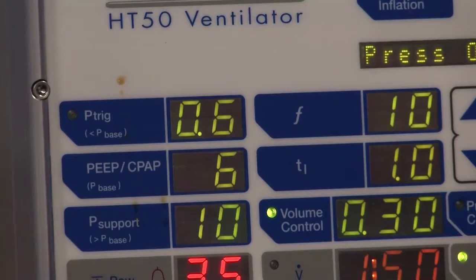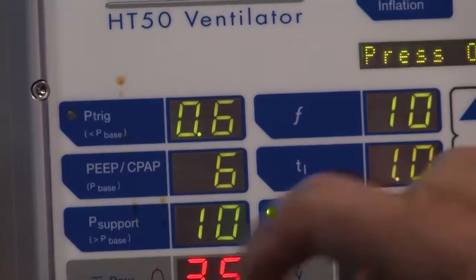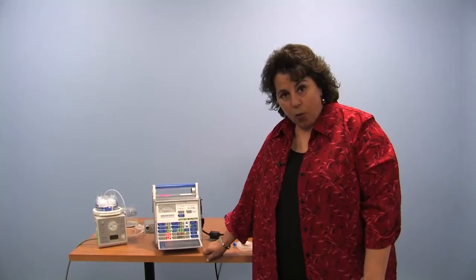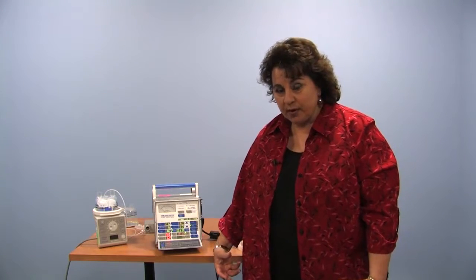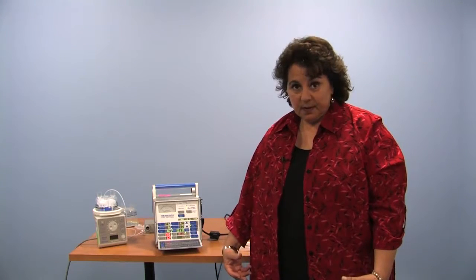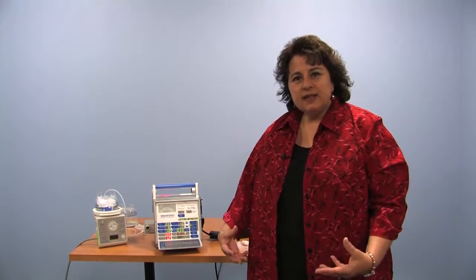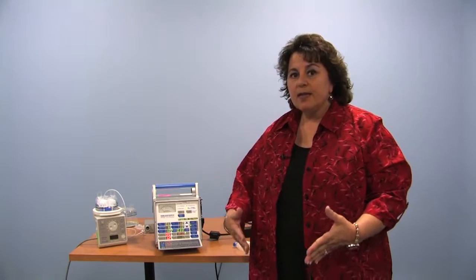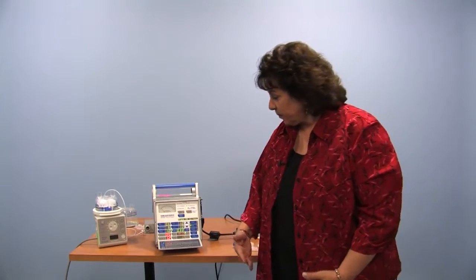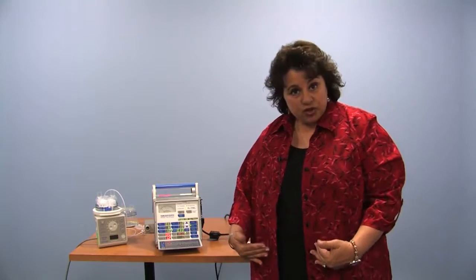The pressure support set on this ventilator right now is 10 centimeters of water. So 10 is the dose or the amount of pressure support above the PEEP that your doctor has ordered for your child to help them decrease work of breathing, but increase the size of the breath they take in between the mandatory breaths if your child's receiving mandatory breaths on the ventilator. If your child is breathing on just pressure support, that would be the support they receive.